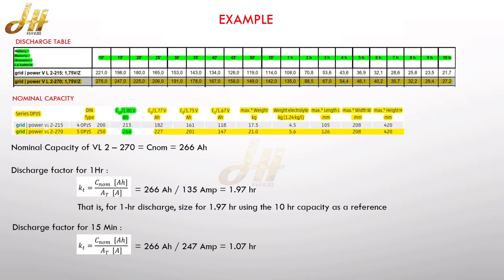And similarly, we can also check the discharge factor for the 15th minute. Similarly, 266 Ah divided by 247, which is 1.07. So this is how the KT factor is calculated.